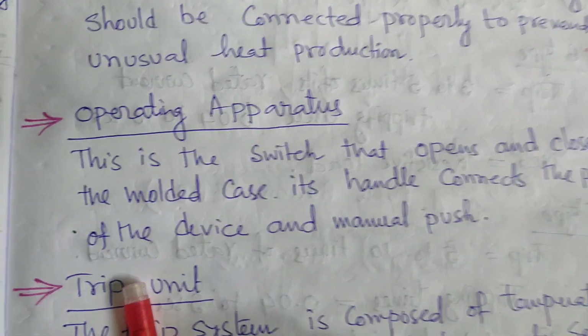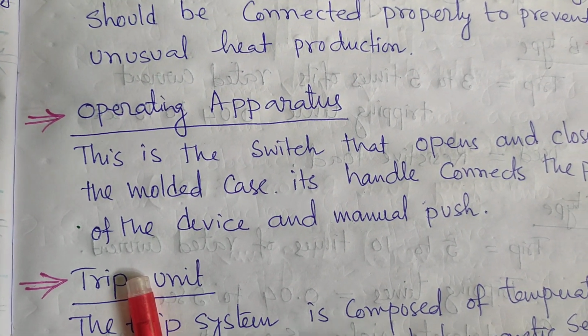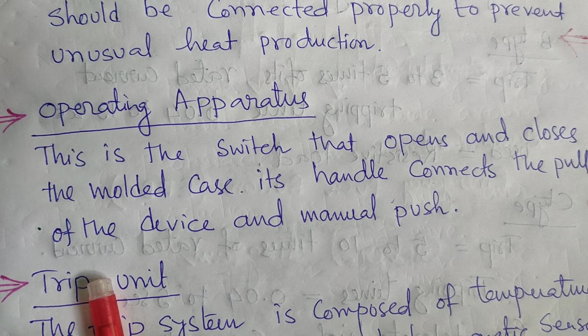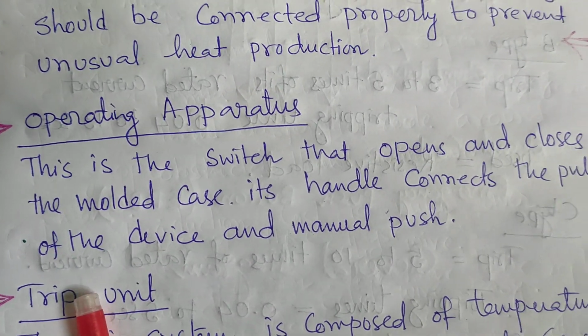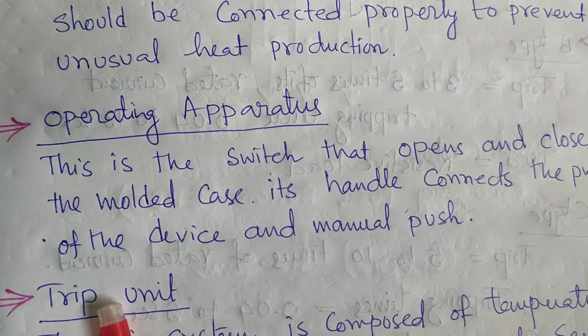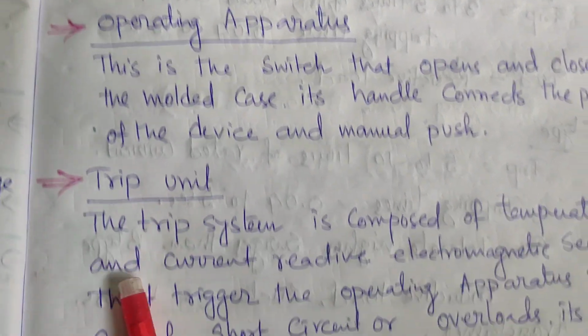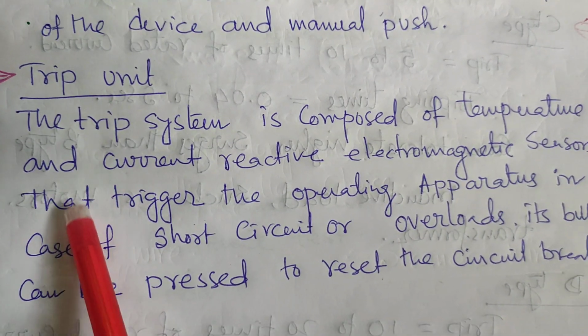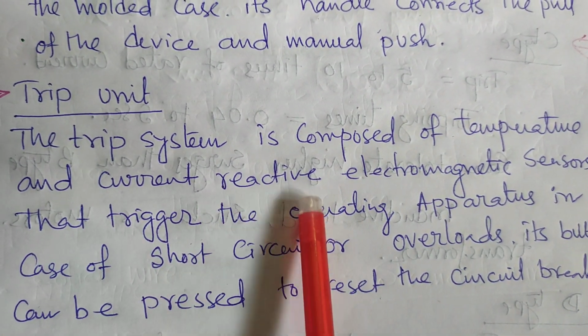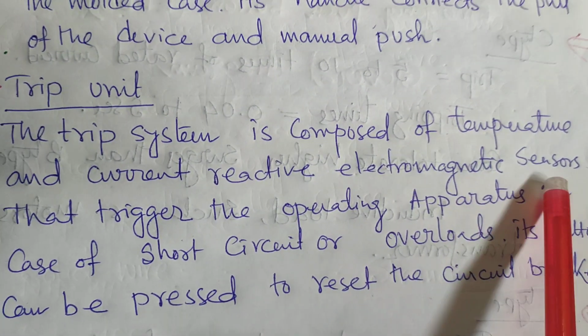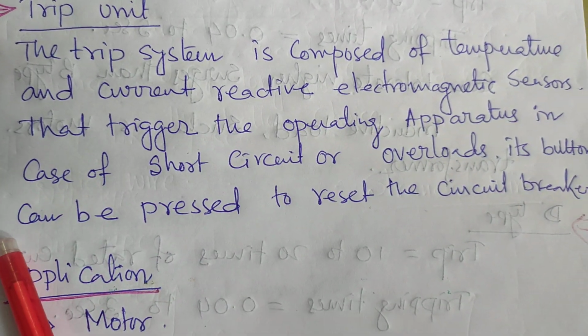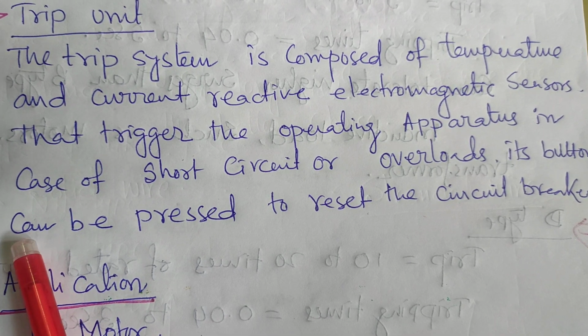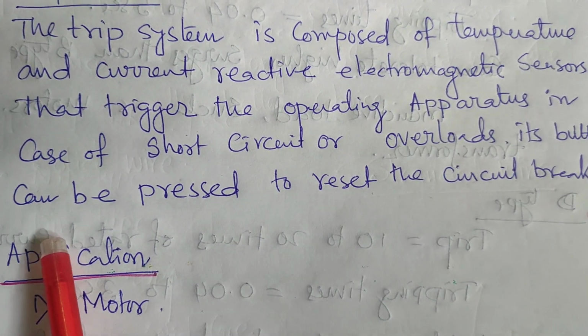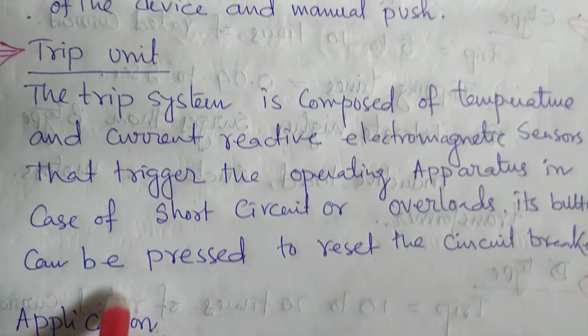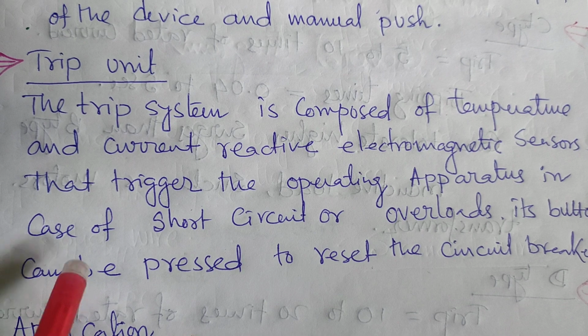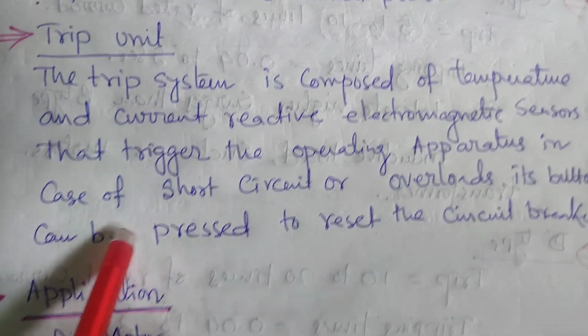So MCCB has a switch that can turn the circuit breaker on and off. This is the switch that opens and closes the molded case, and its handle connects to the pull of the device and manual push. Trip unit. The trip system is composed of temperature and current reactive electromagnetic sensors that trigger the operating apparatus in case of short circuit and overload. Its buttons can be pressed to reset the circuit breaker. So the trip unit can trip the circuit breaker when needed.